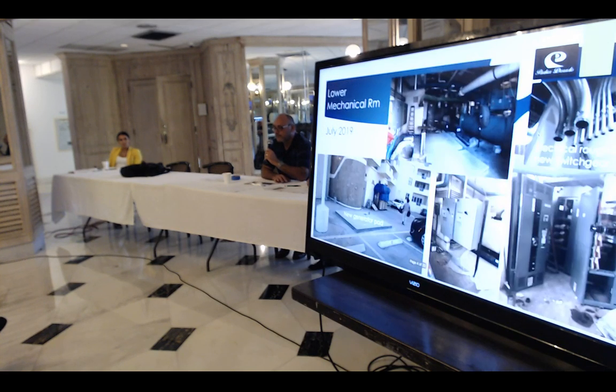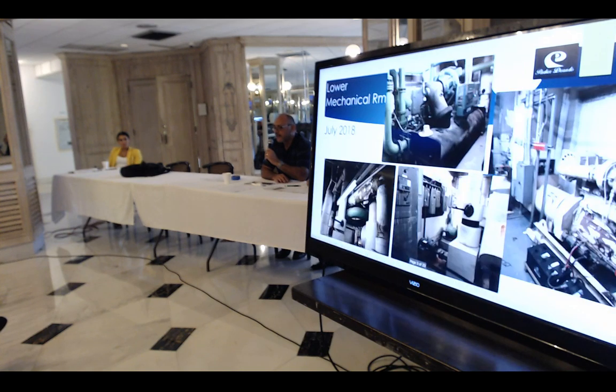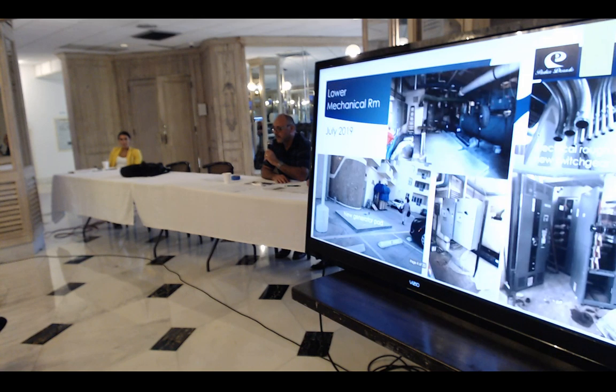Currently in that room, we have housekeeping pads, which are concrete, that required restoration of the existing floor. The floor had some spalling problems where, over the years, moisture gets into the concrete and rebar, causing it to spall and require repair. When the boiler failed and we went to replace it, we found the floor just beneath the boiler was almost non-existent, so that was also replaced, repaired, and brought up to code, with new boilers installed.